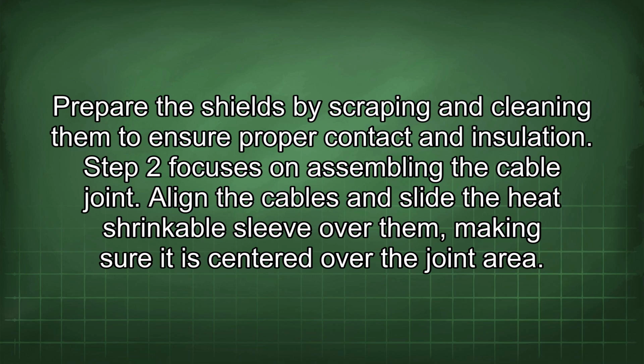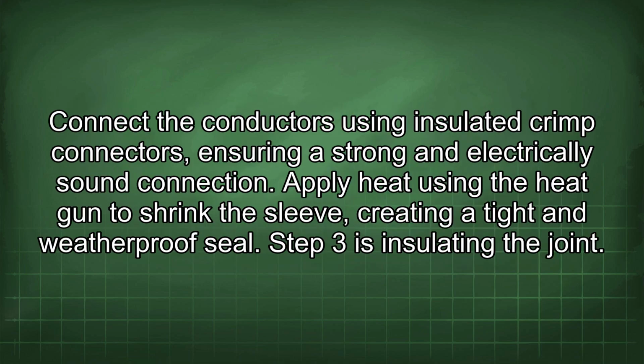Step 2 focuses on assembling the cable joint. Align the cables and slide the heat-shrinkable sleeve over them, making sure it is centered over the joint area. Connect the conductors using insulated crimp connectors, ensuring a strong and electrically sound connection. Apply heat using the heat gun to shrink the sleeve, creating a tight and weatherproof seal.